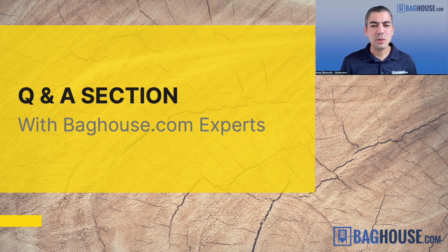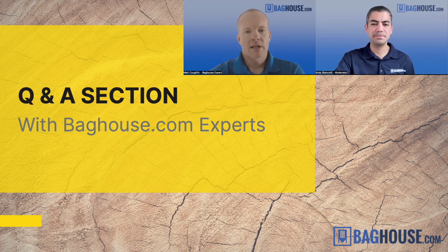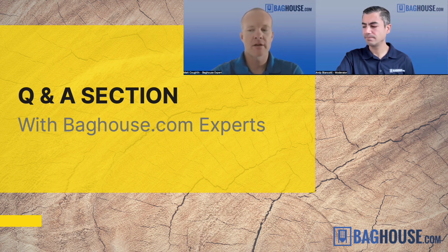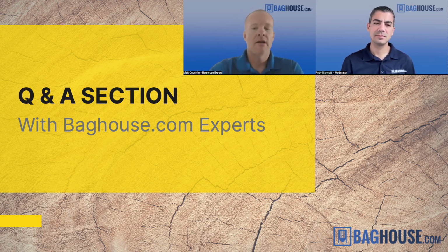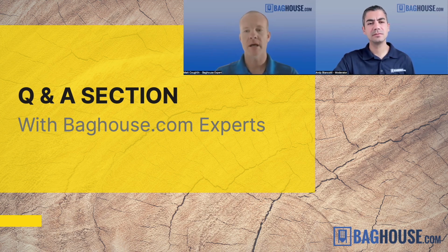Awesome. Next question. What are the warning signs that a dust collection system is undersized or not performing properly? So classic warning signs that your system is undersized or not performing properly. So the basic kind of functional metric for a baghouse or dust collection system is the differential pressure. So that's the pressure across your filters. Usually, they're designed to operate between 2 and 5 inches water. That's kind of the pressure range you're looking for. If you go out and you look at your baghouse and it's pinned at 10 inches, or maybe it's 6 to 8 inches, what it's telling you is that your filters are blinded or your filter cleaning mechanism is not functioning, and it's like a big warning red light for your system. So answer number one is differential pressure too high. That's a big warning sign.